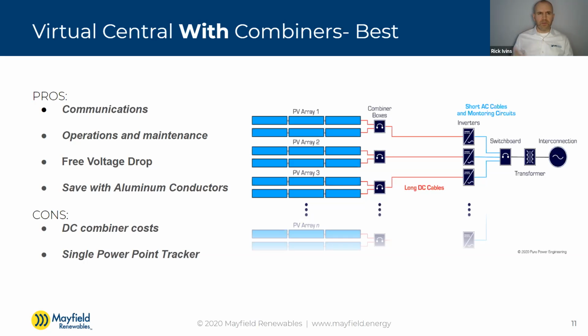A lot of the gear that's rated for 600 is no longer rated for that. So you have to start looking into the gear challenges with that. Real quick, the reason why is with the power electronics, and this will probably improve in a few years, but the power electronics can only make a jump from that DC voltage to AC of a certain amount. You can't do more and still be cost effective.